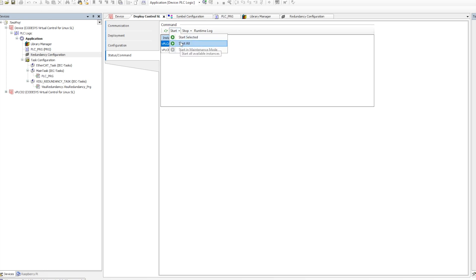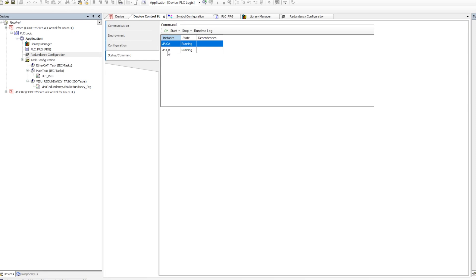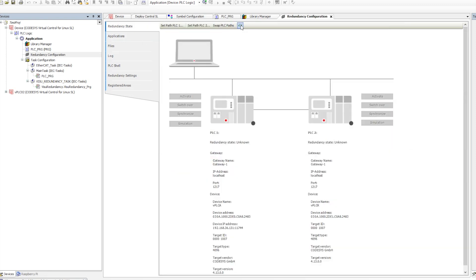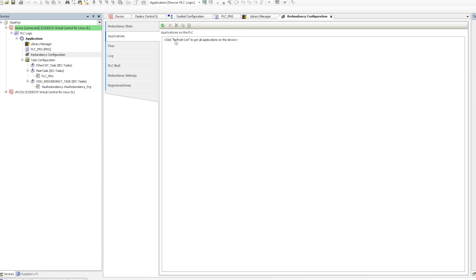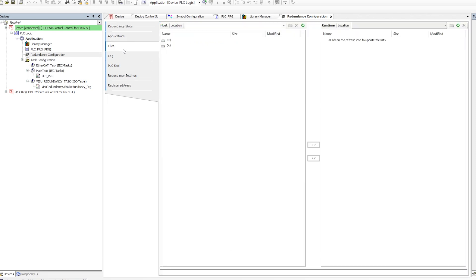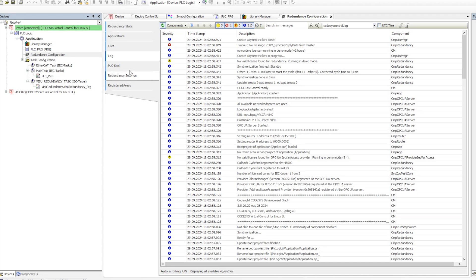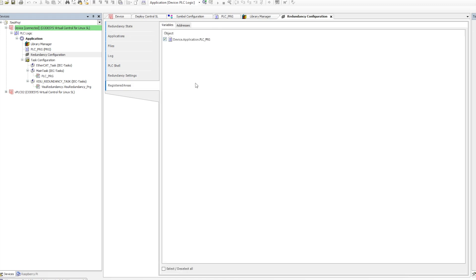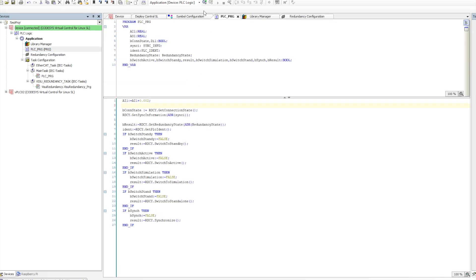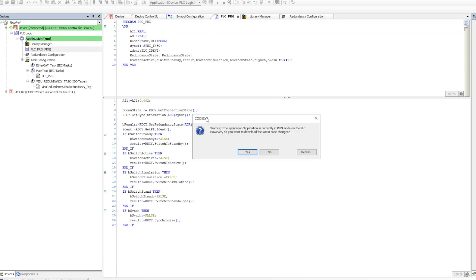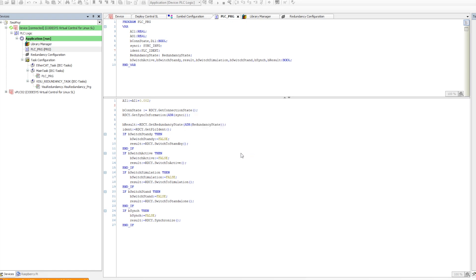It is better to start the PLCs one by one rather than simultaneously, because if both start at the same time they sometimes don't synchronize properly. The active one should be started first, and then the redundant passive one. You can see they come into active and passive states, and the application gets loaded into the second PLC. In the log, you can see keys created and redundancy settings applied.